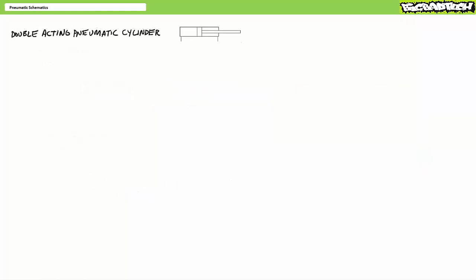Double acting pneumatic cylinders, in contrast, have both a rod end port and cap end port. Whereas single acting cylinders only actively perform one movement and passively perform the opposite via a weight or a spring, double acting cylinders actively work on both extension and retraction. The act of extending a double acting pneumatic cylinder routes pressurized flow to the cap end and exhausts the rod end. In contrast, the act of retracting a double acting pneumatic cylinder routes pressurized flow to the rod end and exhausts the cap end.